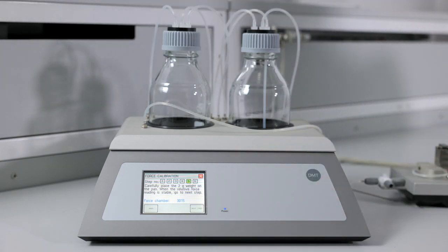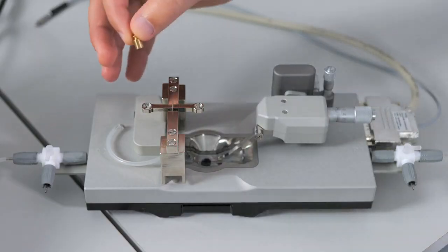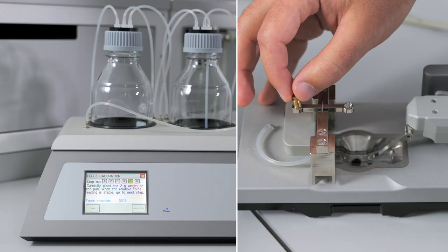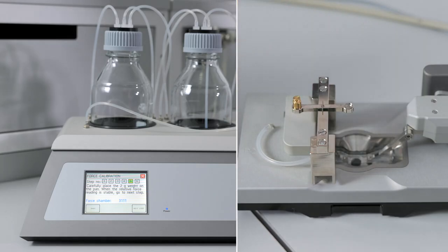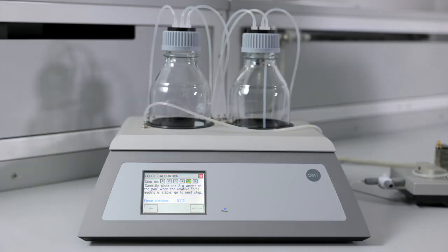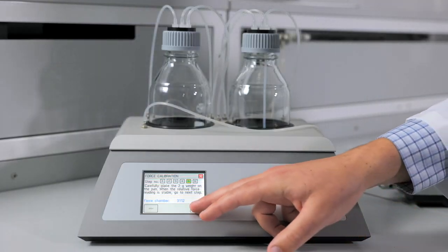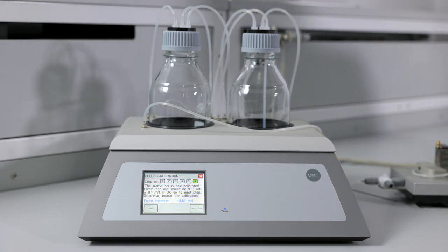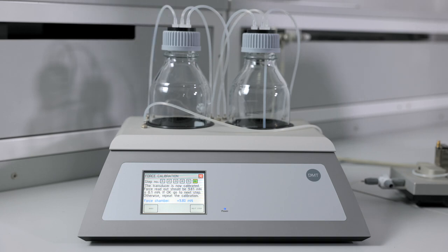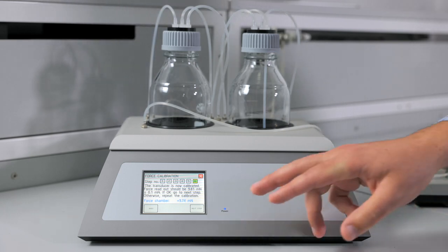You are now asked to place a 2-gram weight on the calibration bridge. You will place it on the left side of the bridge, which will add force to the transducer. Give this 20 to 30 seconds to stabilize, and then go to the next step. This number should be approximately 9.81, and as long as it's within 0.1, you can conclude the calibration by clicking next step.